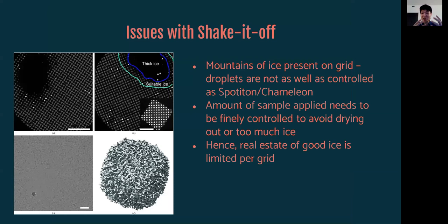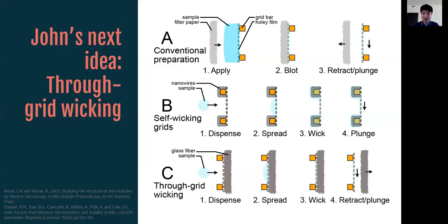However, this first generation Shake It Off device does have its drawbacks. So as you can see, a conventional atlas from this grid, you have thick ice in the middle and then no ice around the other side. And the usable ice is only this little fringe ring region around the thick ice. So that is very small area of usable ice, which is not good. This is likely because of the way that we apply the sample using the piezo. So the droplets in the mist are small, but they are not as small and finely controlled as the Spotiton or Chameleon droplets, which are emitted through an ink-jetting technology. Therefore, there's still a Gaussian distribution and the droplets actually saturate the nanowire's capacity to actually absorb the liquid. Therefore, you still get thick ice in this region, even though these regions around here are thin. So that results in a very limited real estate of good ice in these grids. So it limits the ability of Shake It Off to produce consistent grids.